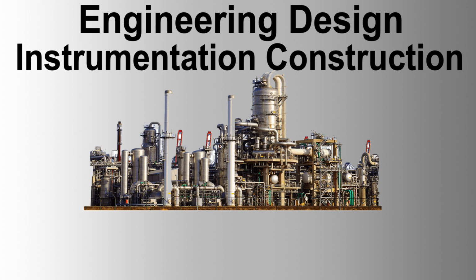Documentation. Detailed records of all loop tests shall be maintained. This includes documenting the test procedures, results, and any issues identified during testing. Any deviations from the expected results shall be investigated and resolved. The resolution of any issues shall be documented. Test records shall be submitted for approval and kept as part of the project documentation.